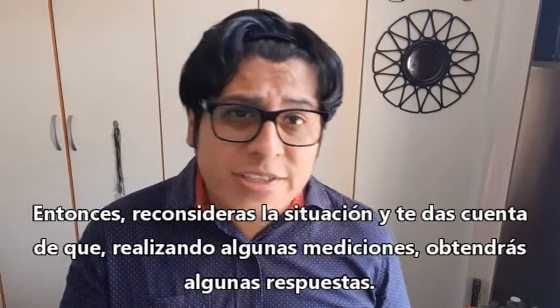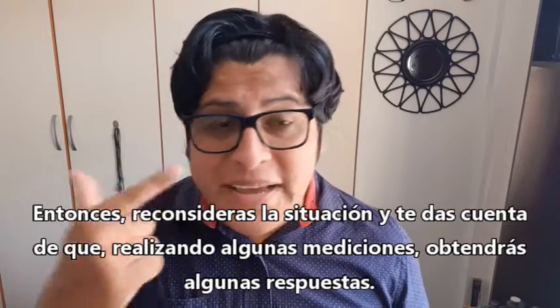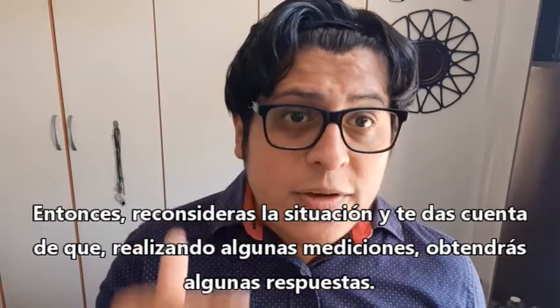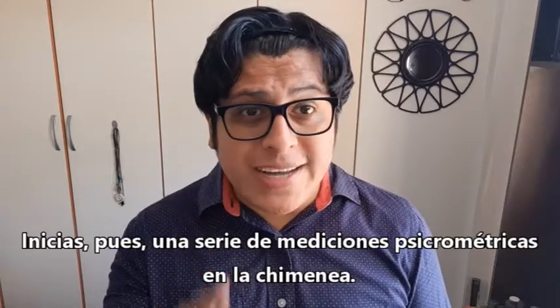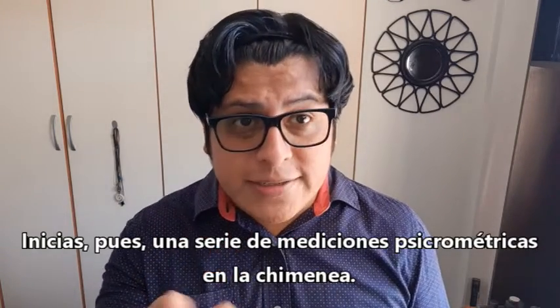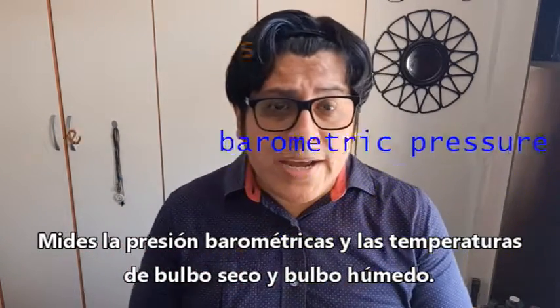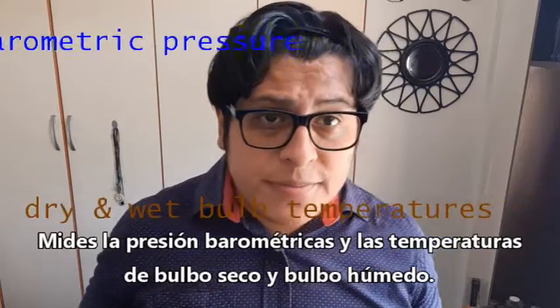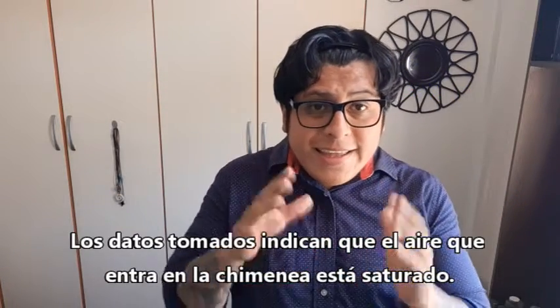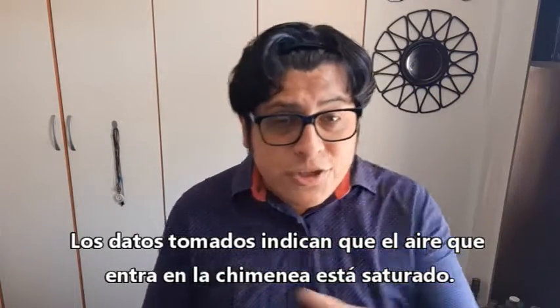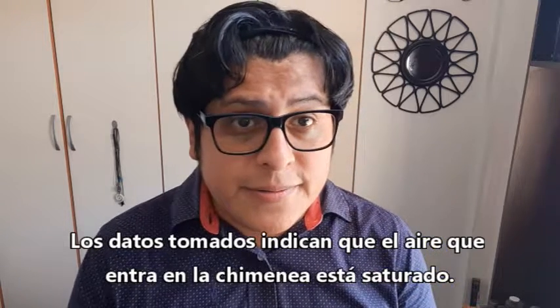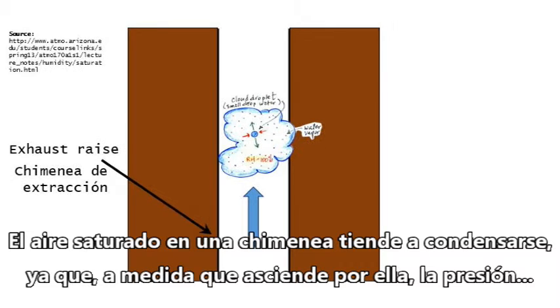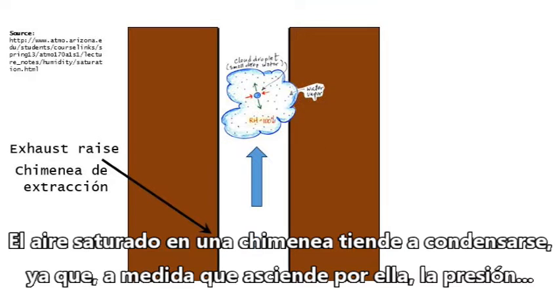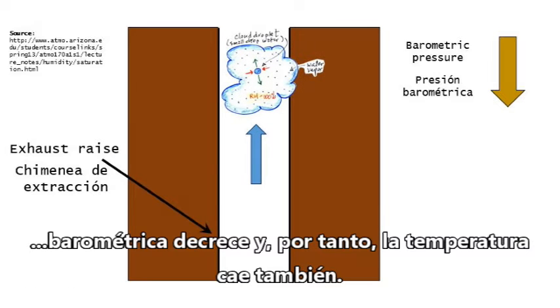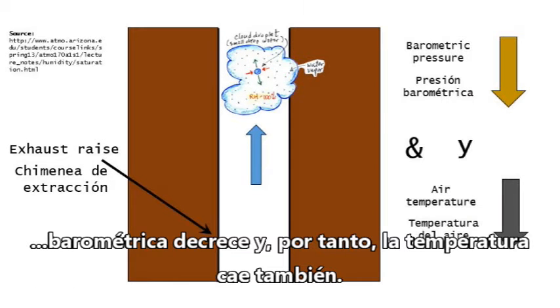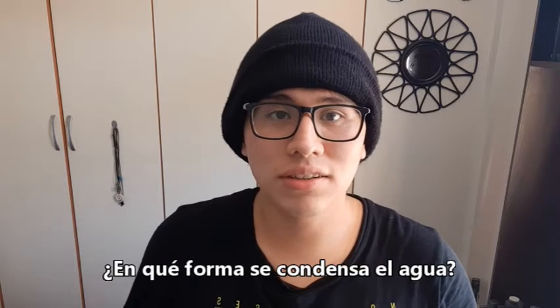But then you reconsider this issue and understand that measuring some data will give you some answers. So you start a psychrometric survey on the raise. You measure barometric pressure and dry and wet bulb temperatures. The data you gather indicate that the air that enters the raise is saturated. Saturated air in an exhaust raise tends to condense because as it goes up through the raise, the barometric pressure decreases and thus the air temperature falls. How does the water condense?